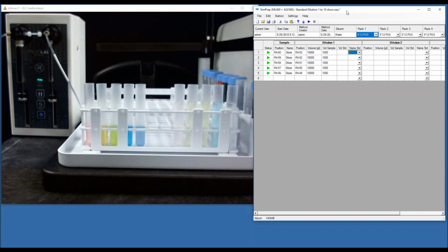but we have been able to get really good accuracy results for something the size of 100 microliters with the standard carbon fiber. And the issue that you run into with using a small probe or something that's specifically designed for low volumes is then you have to also reduce the speed of the syringes so that you don't cause a pressure buildup and potentially damage the syringe. So at this point, we're just using the standard 1 ml probes to try and reduce the restriction on the line as much as possible. But we have been able to get good data with that for something as small as 100 microliters.